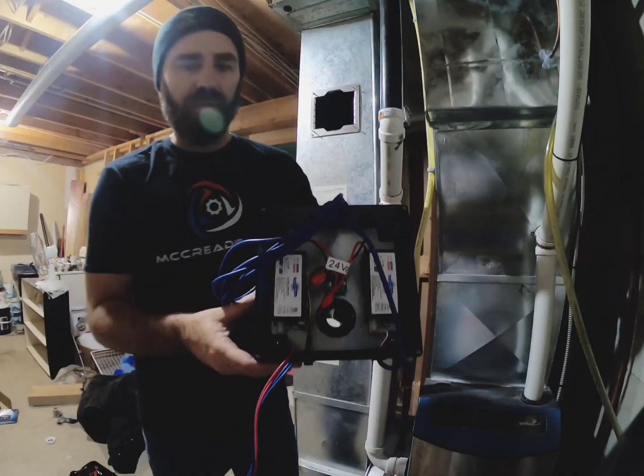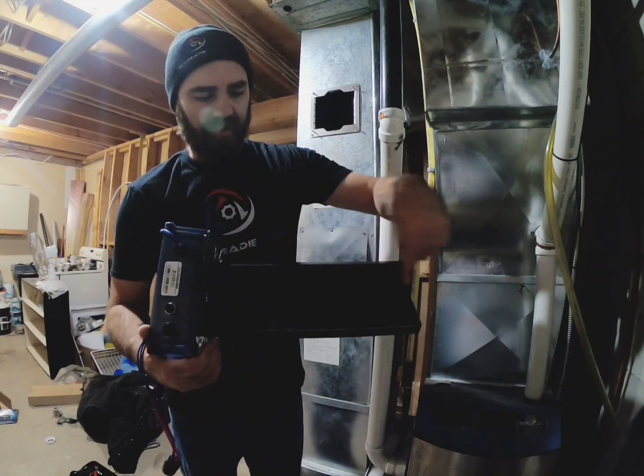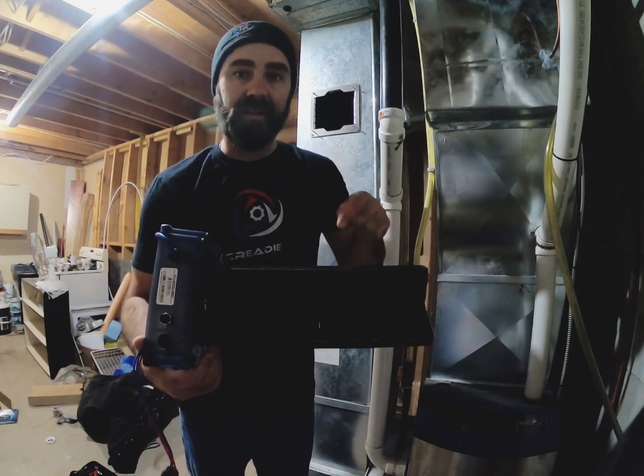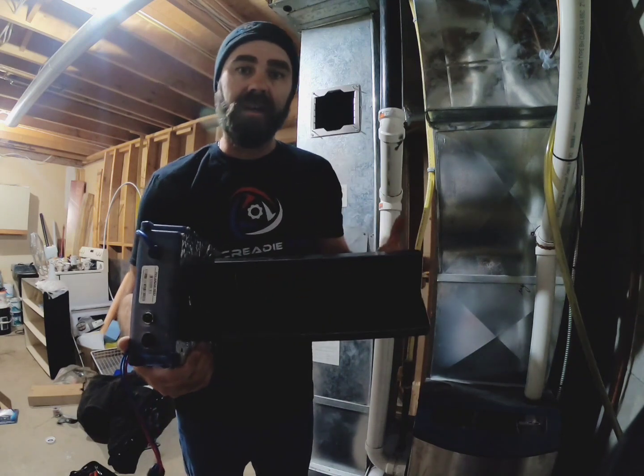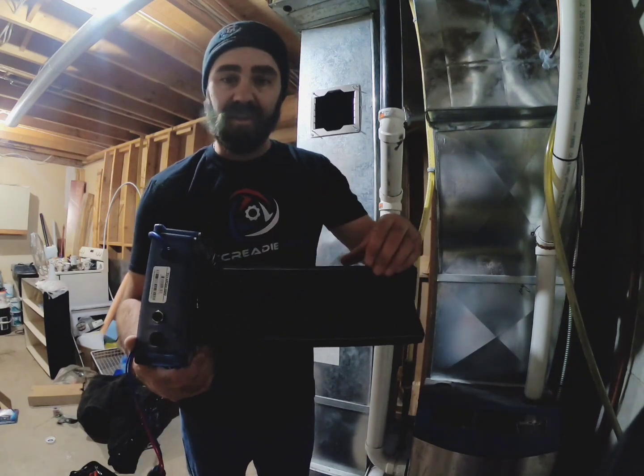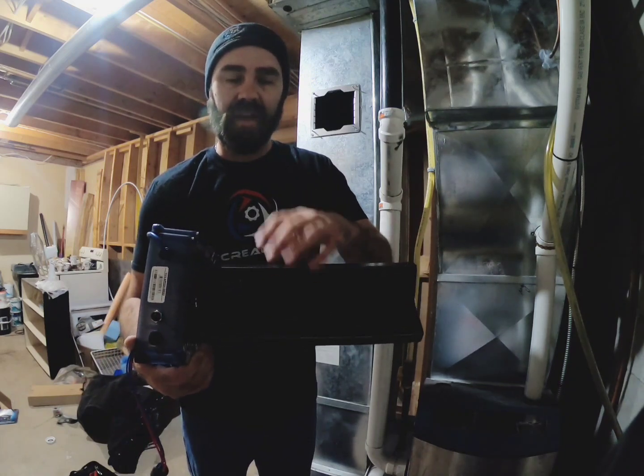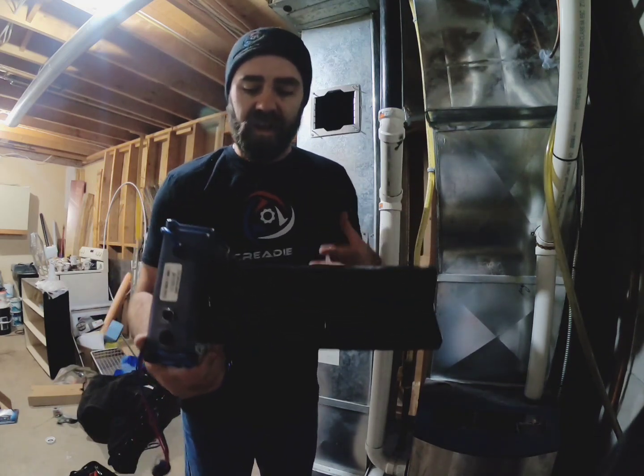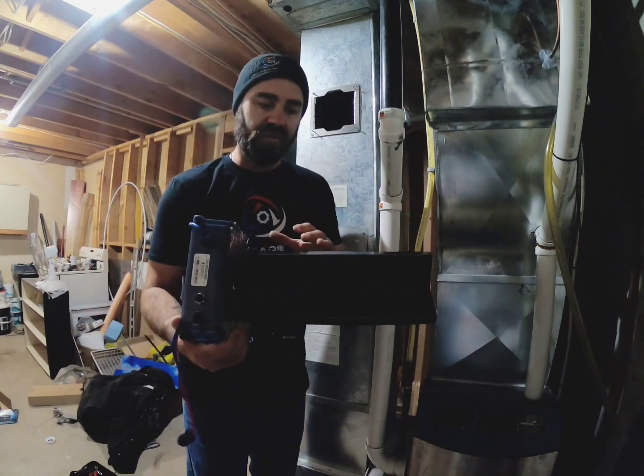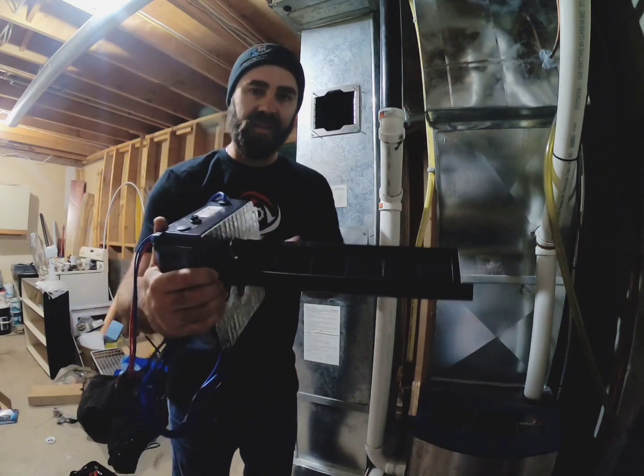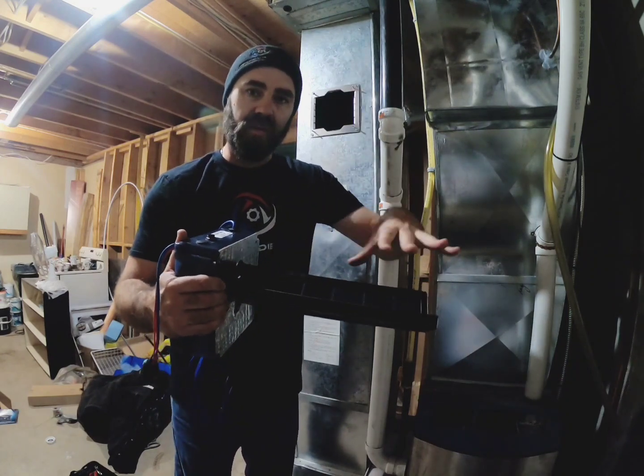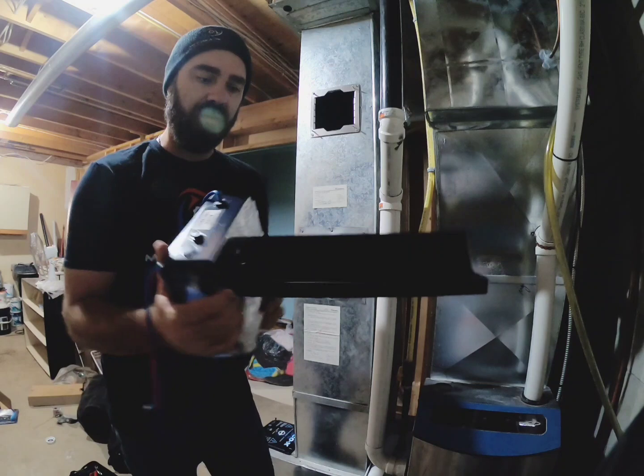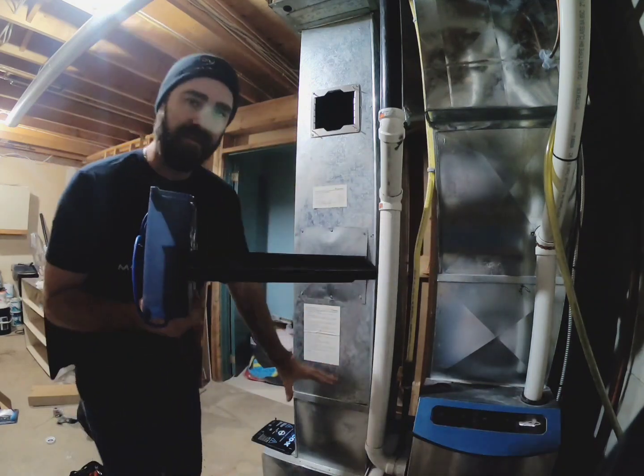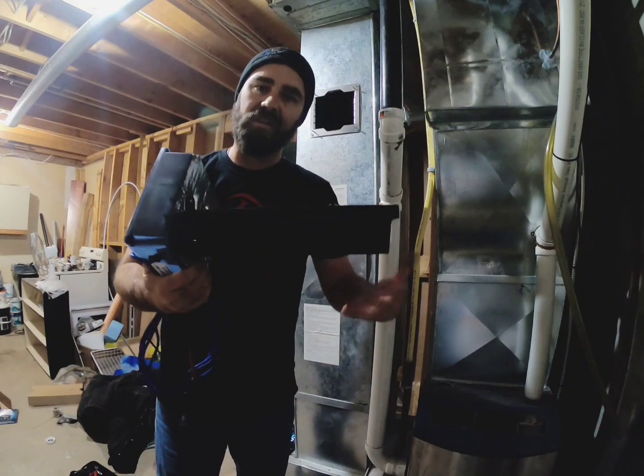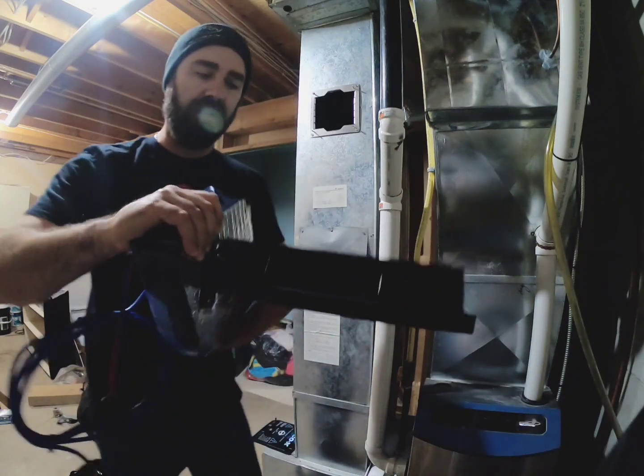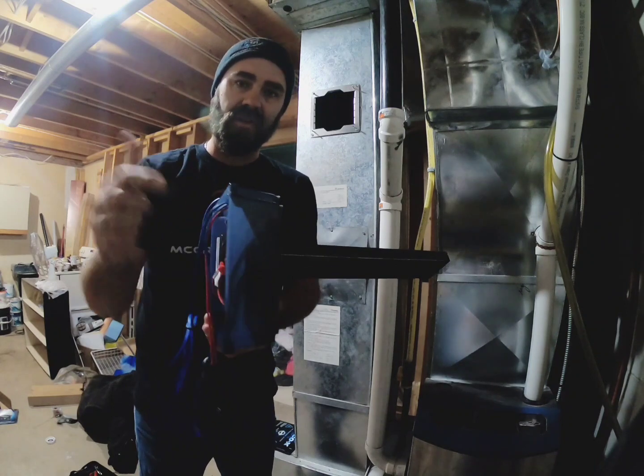So here's the unit opened up with the cover off. And if we look on this long piece here, this is our carbon matrix. This is our titanium infused carbon. And it's unlike activated carbon where this doesn't become saturated, it keeps regenerating. So we always have that carbon to get rid of the odors in the air. And what's really important about installing these on the return side is we want to have the airflow coming down and hitting the UV light first and then the carbon matrix. And the other reason for that is we don't want the UV light shining down potentially on the filter media because the UV light can start to deteriorate that filter media. So we want to install it basically upside down, just like this on the return side.